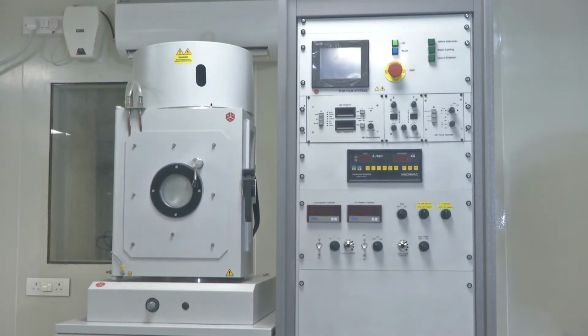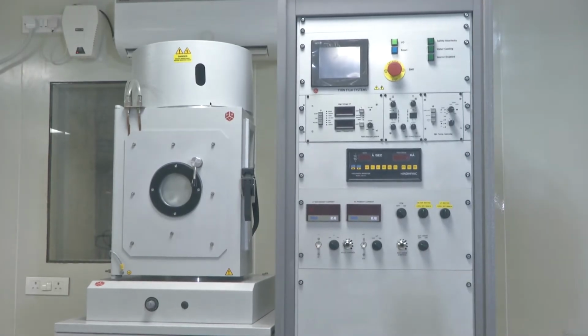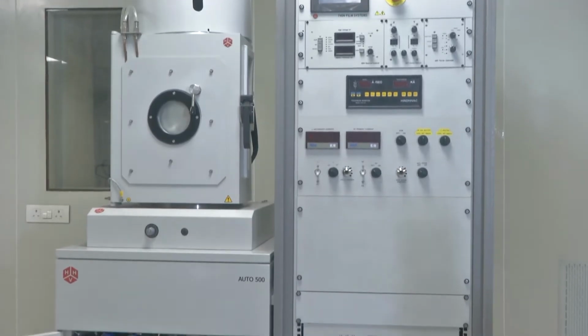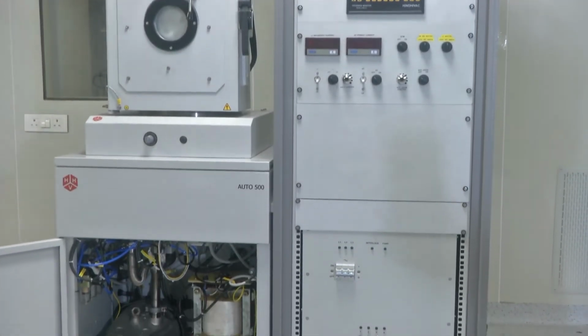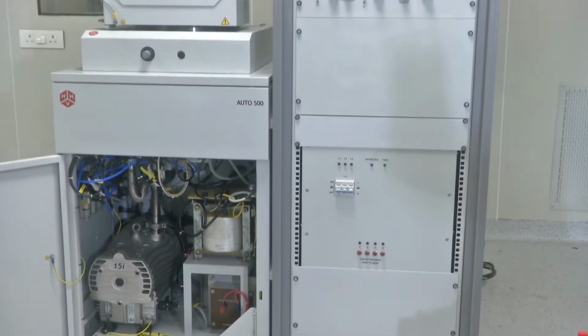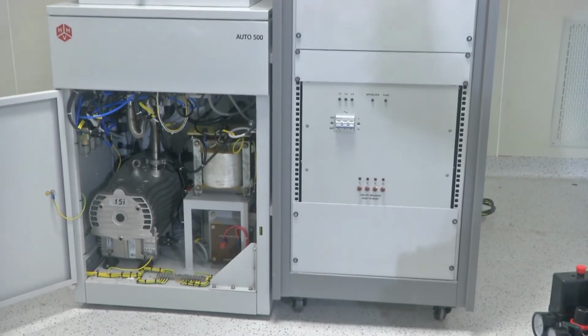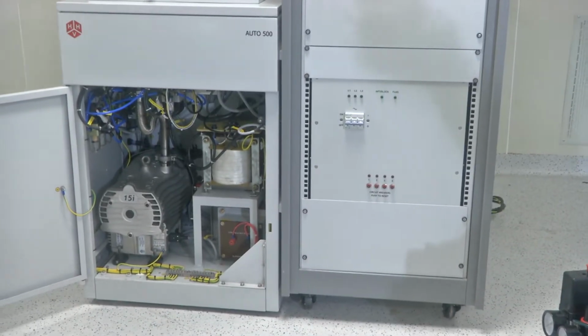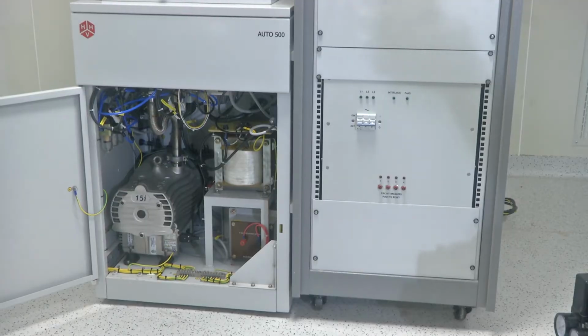See, initially, first switch on the rotary pumps. Wait until the backing line reaches better than -2. Then switch on the turbo. For switching on the turbo, you need water also. Without water, the turbo is not switched on. It needs cooling water. This is a water-cooled turbo molecular pump.